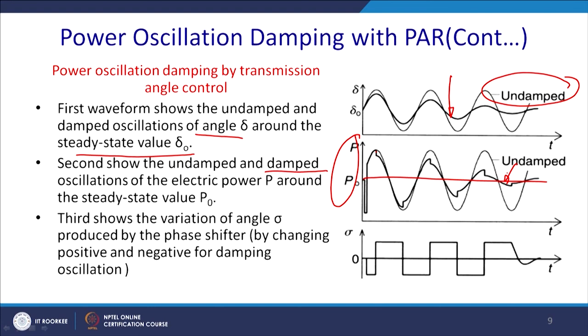The third shows the variation of angle delta sigma produced by the phase shifter. Gradually, you will change the phase of it. Generally, it starts at quadrature and accordingly will change. Since the change in delta is positive, you inject the negative phase to bring it down, and you inject the positive phase to bring it up when the change in delta is negative. So, by the phase shifter, by changing the positive and the negative damping, by changing sigma, you gradually bring the angle delta down to the steady state value. Thus this can effectively damp out the power oscillation. Thank you for your attention.